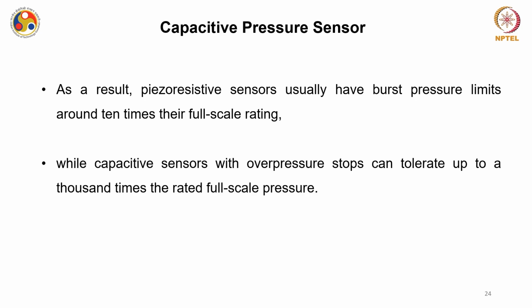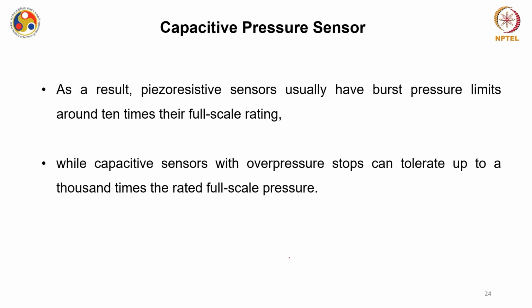So when you are dealing with low pressure, these things become very, very important. For example, you are measuring in the range of say 1 Pascal, and suddenly a pulse of say 100 Pascal or 1000 Pascal is applied. Your piezoresistive sensor is going to break in that case, because the burst pressure limit is not more than 10 times. So if the full scale rating was 10 Pascal, it cannot go beyond say 100 Pascal, because that is its burst limit.